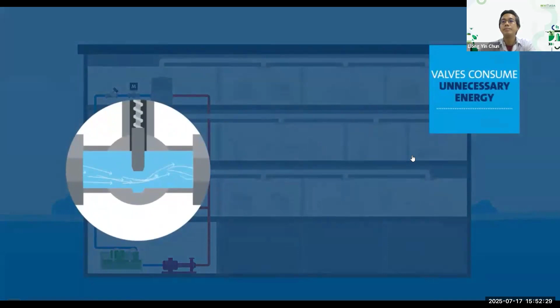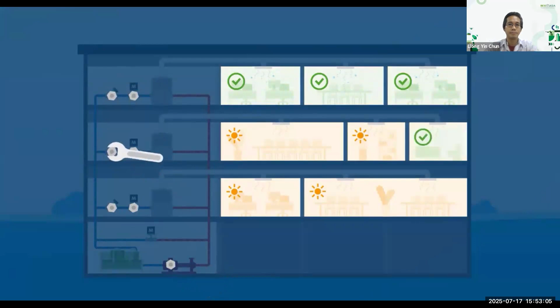Furthermore, a bypass line is typically used in the system to ensure sufficient flow to the chillers. Cooling systems with central pumps and valves have been designed in this way for decades. However, there are issues shared by existing cooling systems that lead to high energy consumption and less comfort in the building. One is commissioning and balancing, which is traditionally a time-consuming and tedious procedure, but essential for ensuring a system that operates to its highest potential.